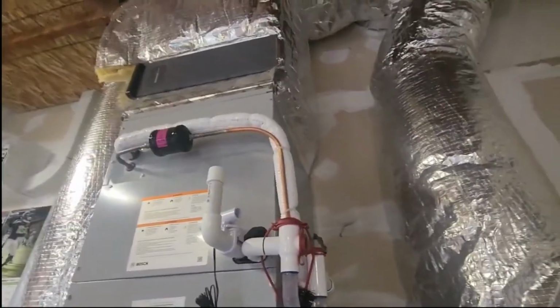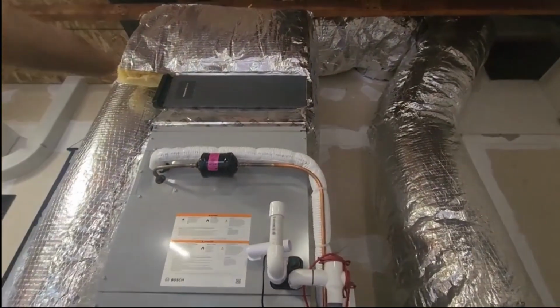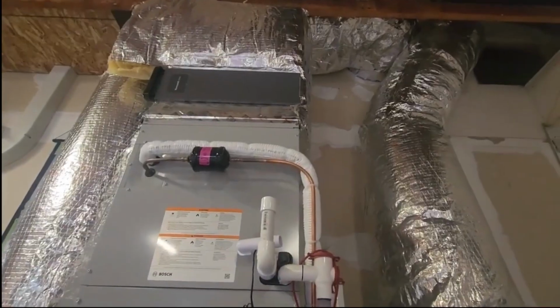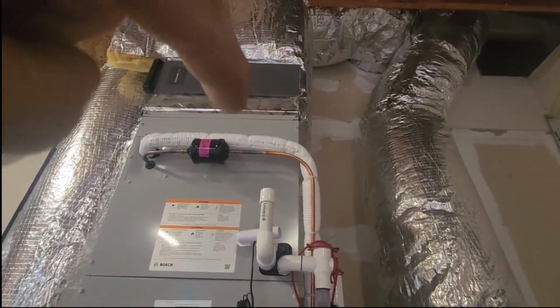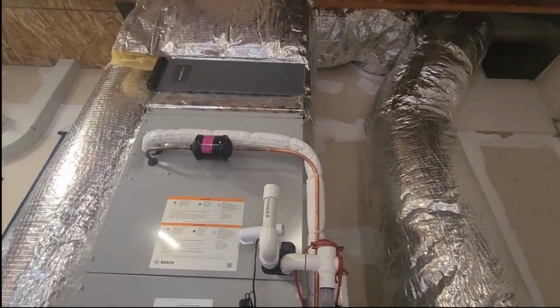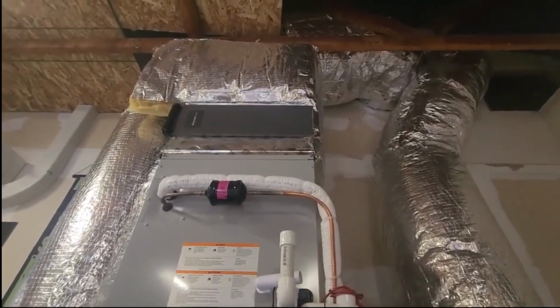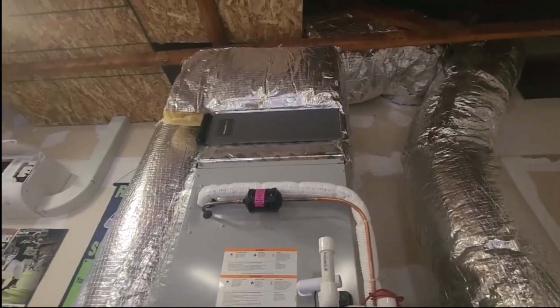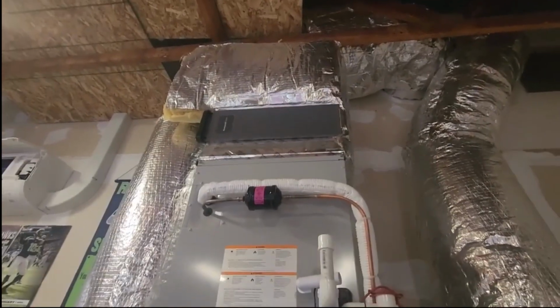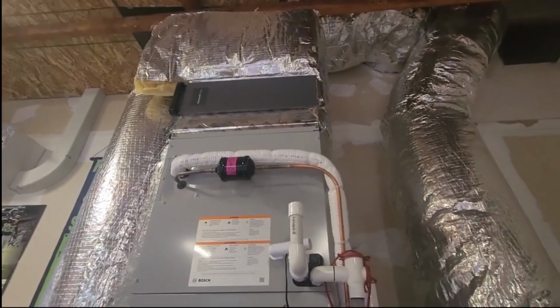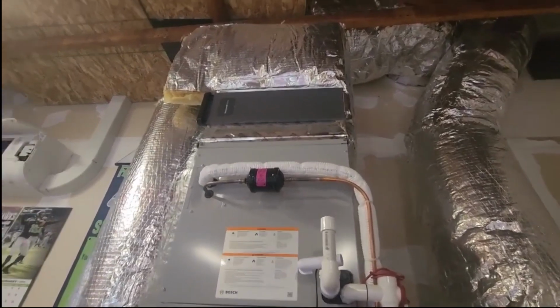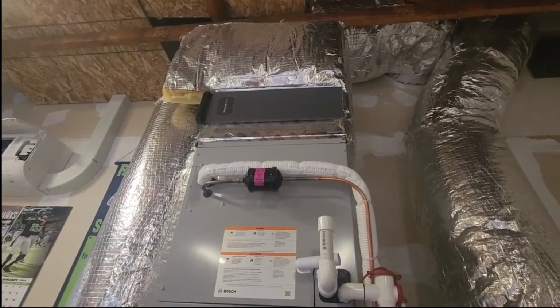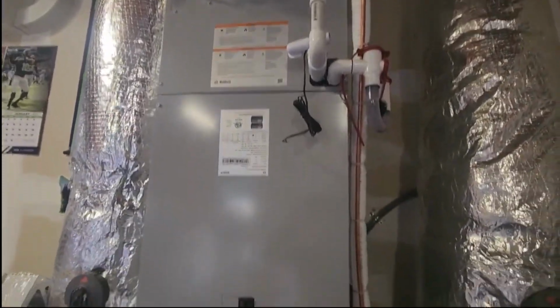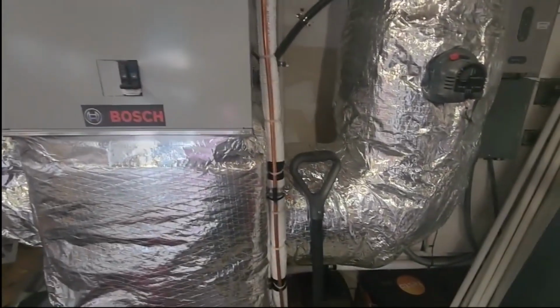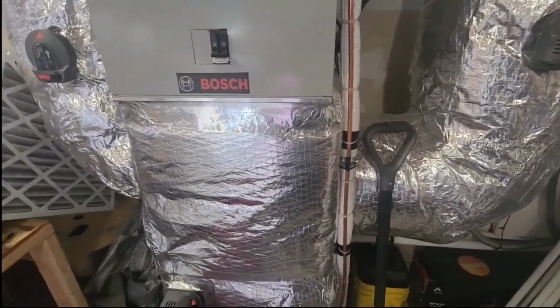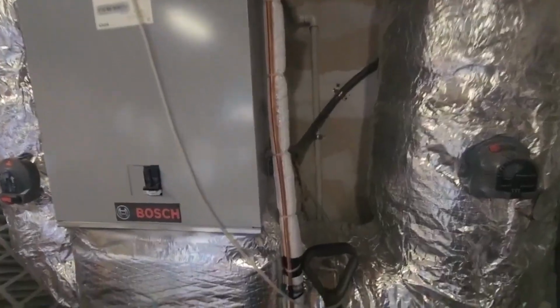I got a spacer. I always put a spacer between the air handler and the filter, so I'll be able to get a probe there and a probe there and see what the filter's giving us. I just replaced the filter, so that'll be a good lesson on what static pressure these 4-inch filters have when they're clean. I'll get some holes drilled, and then we'll get the equipment set up and I'll show you how that works. I'll force this thing into cooling, both zones. I'll be back. Okay guys, we're all hooked up.